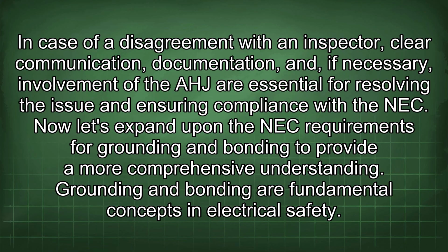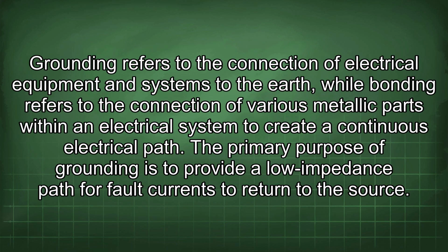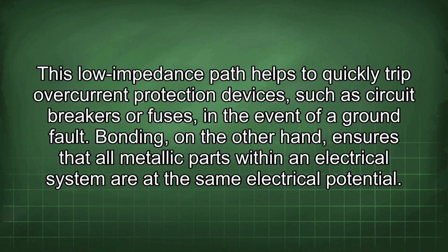Now let's expand upon the NEC requirements for grounding and bonding to provide a more comprehensive understanding. Grounding and bonding are fundamental concepts in electrical safety. Grounding refers to the connection of electrical equipment and systems to the earth, while bonding refers to the connection of various metallic parts within an electrical system to create a continuous electrical path. The primary purpose of grounding is to provide a low impedance path for fault currents to return to the source. This low impedance path helps to quickly trip overcurrent protection devices such as circuit breakers or fuses in the event of a ground fault.